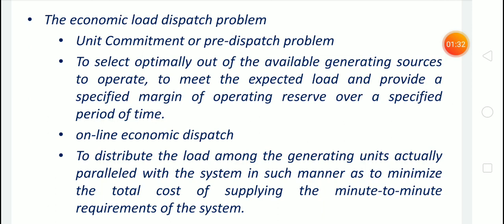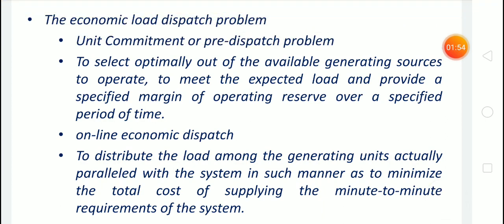In unit commitment, generators are selected optimally so as to meet the expected load, and it also provides some reserve capacity. In online economic dispatch, the available load is distributed among the generating units connected in the system, and it is done so as to minimize the total cost of generation.